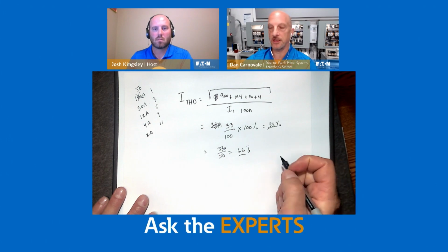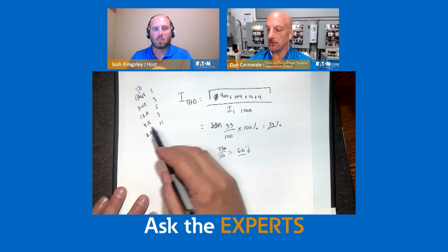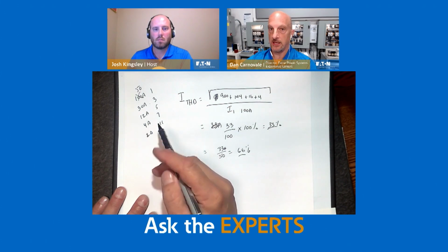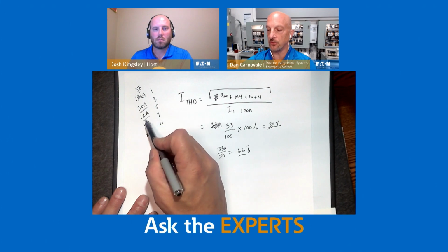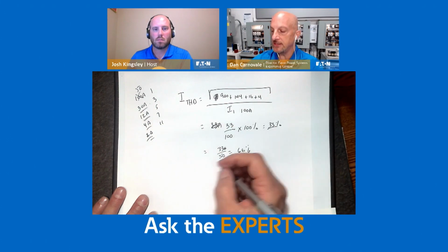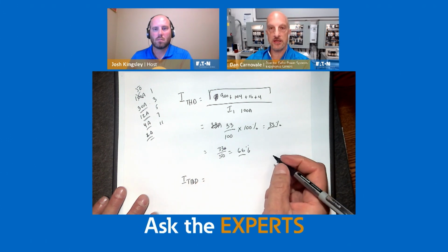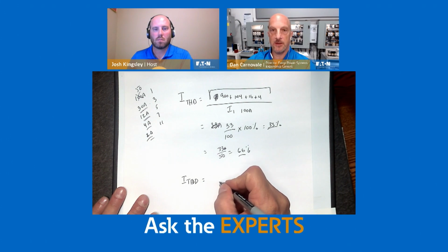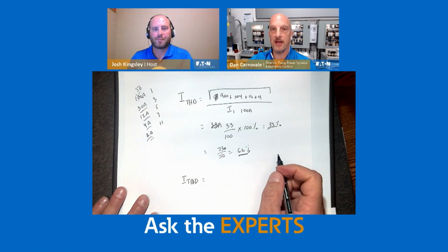And this is where THD can get you in trouble. It's really the same. The same amount of harmonic current is flowing through my power system and heating up my equipment in actual amps. And actual amps are the most important part. What TDD attempts to do is make sure that you're using the maximum demand number so that you're not artificially giving a THD that's way high.